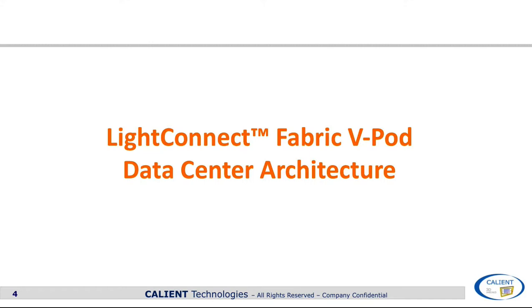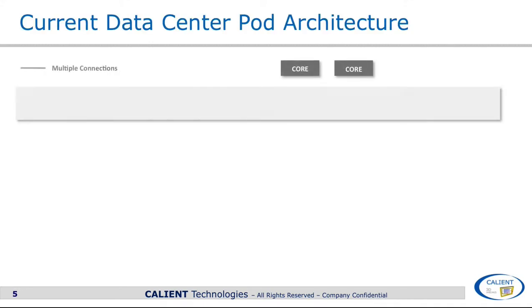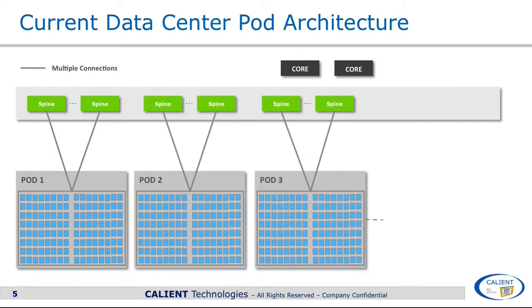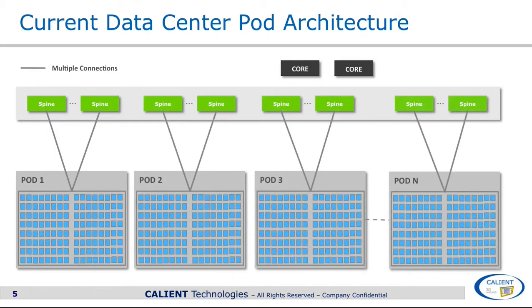Typical large modern data centers are organized into physical pods. These pods are usually the increment of upgrades in large data centers and typically have common failure modes like power or common cooling. Within the pod, servers and storage are organized into modular racks and rows of racks. An example pod configuration might consist of 16 rows, with each row having 8 racks of servers and storage resources as shown here. In data centers today, architects overbuild each resource pod with compute resources to handle peak demand.